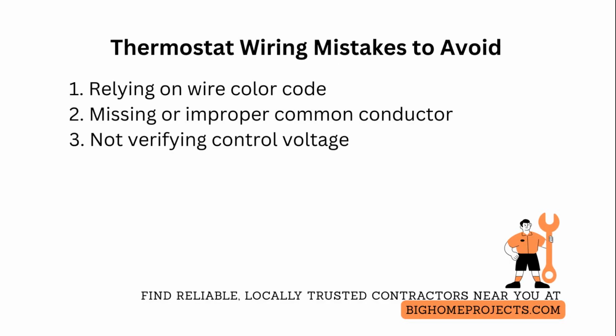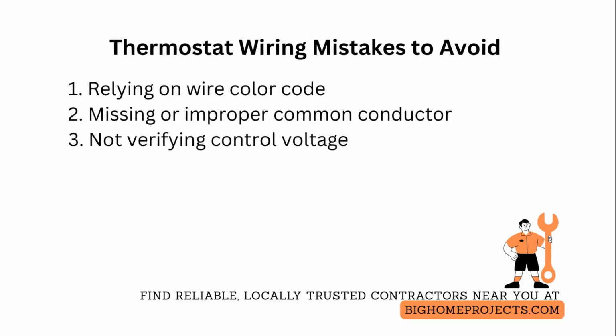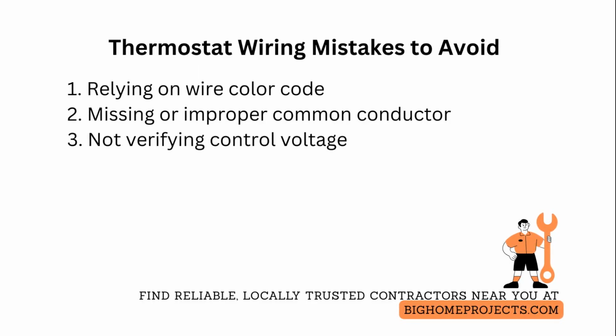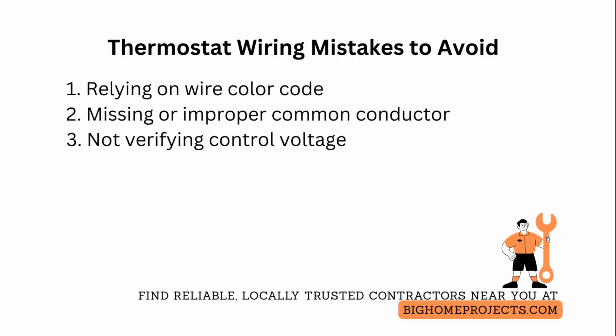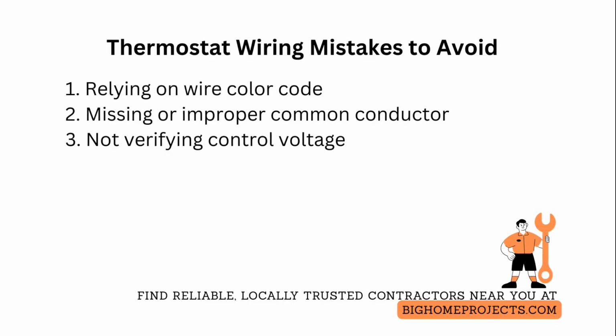One of the frequent errors is not verifying control voltage and system type, which can let you hook up a thermostat designed for 24-volt alternating current to a millivolt or line voltage system. Prevent this by measuring voltages at the control board, reading the equipment data plate, and referring to both the thermostat and equipment manuals before making connections.